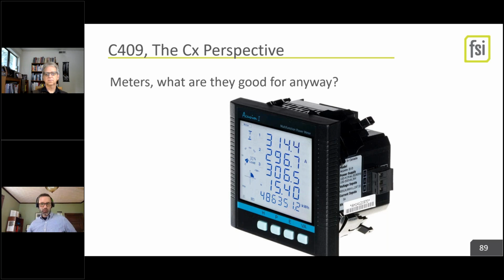Even at the holistic whole-building level, you can compare this year to last year, or this temperature this time last year, and see if you still got that result. You'll watch your building go out of tune - all buildings do over time - and you can decide what's too far out of tune, where you want to retro-commission and bring it back. You can lay this out so you only need a handful of meters, but we see so many systems we commission that have 30 or 40 meters because they weren't laid out well. It wasn't thought about at the beginning of the design, so they just tack on meters everywhere. If you think about this ahead of time, you can be smart about your electrical riser and limit the cost of the system - something to talk to your electrical engineer about.